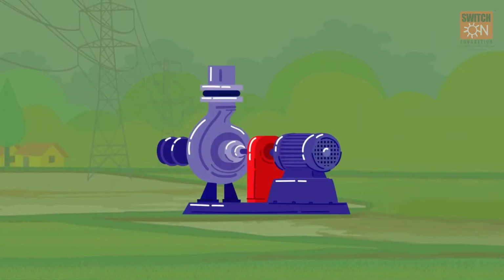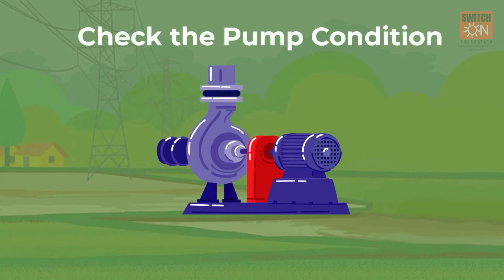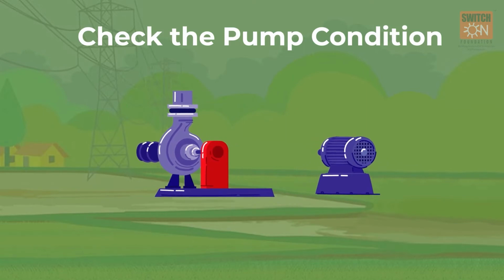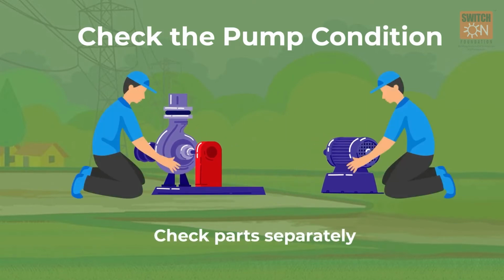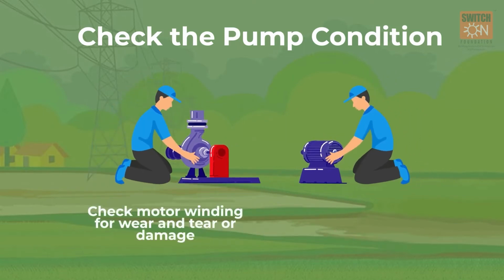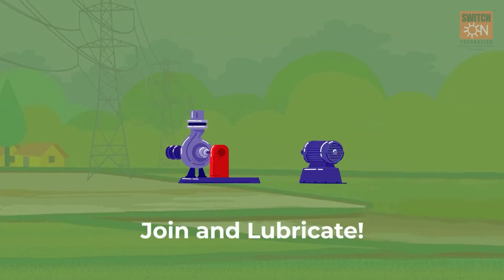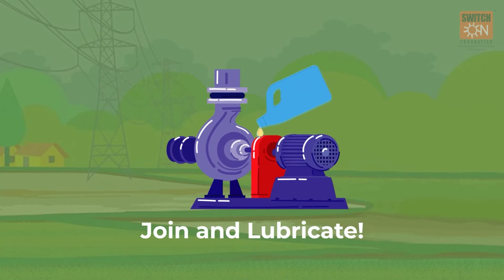In the fifth step, the pump condition needs to be checked. For surface pumps, the motor and pump set are opened separately and checked. 1. The motor winding is checked for any wear and tear and damage. 2. The pump must be checked for any blockage or jam that needs to be cleared. Once checked, the pump and motor must be joined and lubricated.